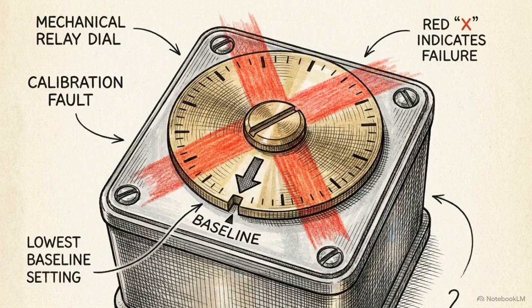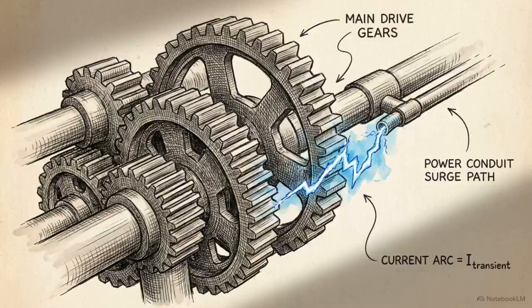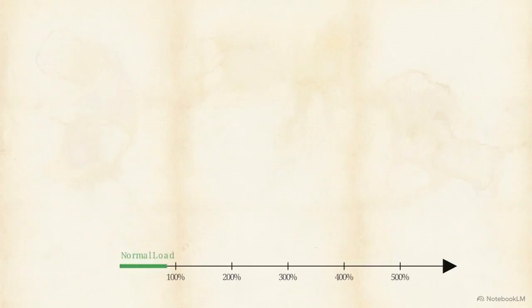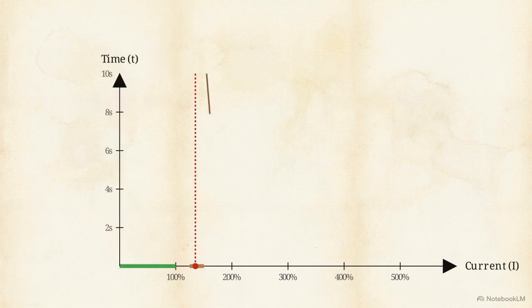A common mistake is setting the relay's pickup current exactly at this 100% mark. Setting it this low guarantees nuisance tripping. It fails to account for normal, harmless transient surges that occur when equipment powers on. Instead, the correct and safe pickup current threshold must be set between 125 and 150% of the full load current.